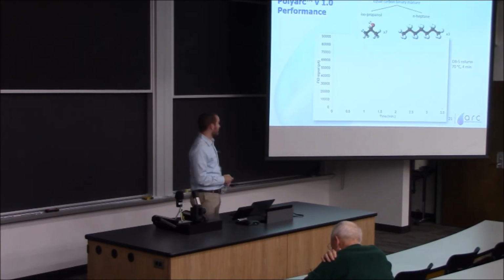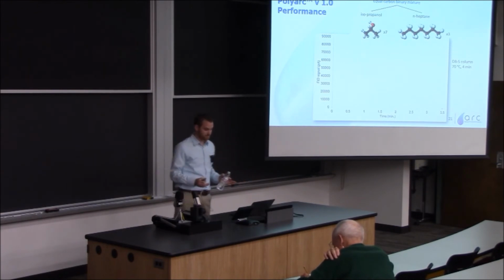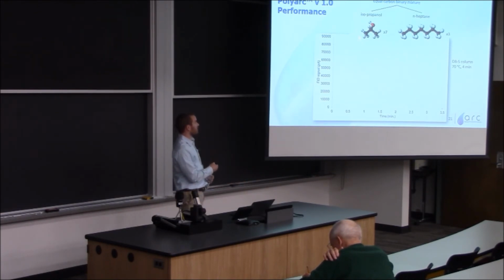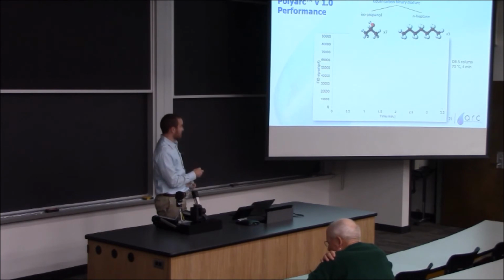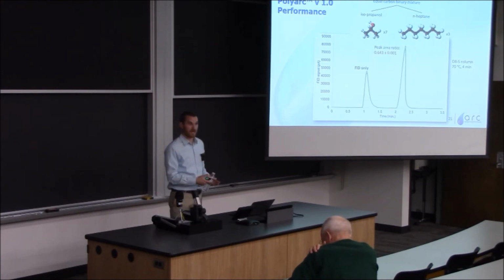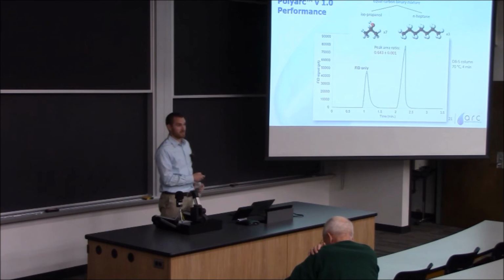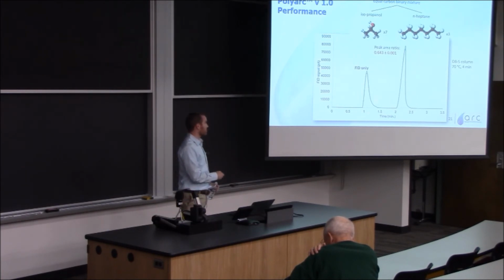To illustrate this point further, I'll give you two examples. In the first example, I want to inject an equal carbon mixture of isopropanol and heptane. When I put those into an FID without the reactor present, I see that the area of the isopropanol, again, there are just as many carbons in this as there are in heptane, is 64.3% that of heptane.